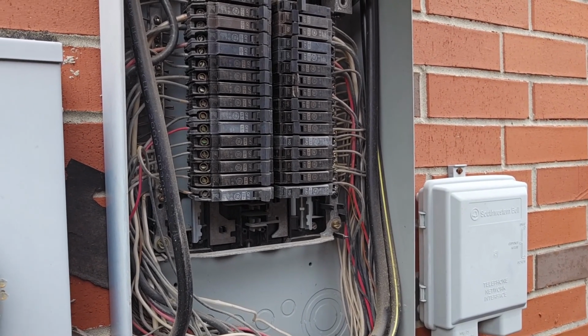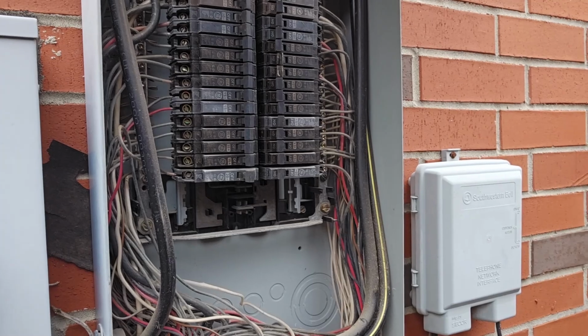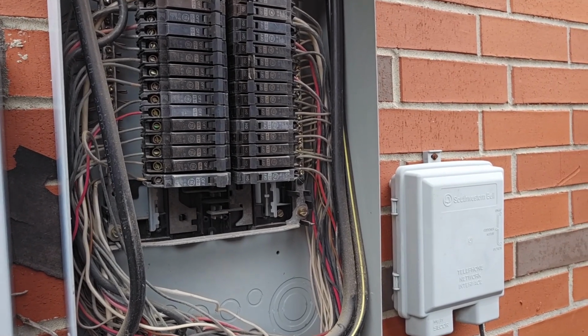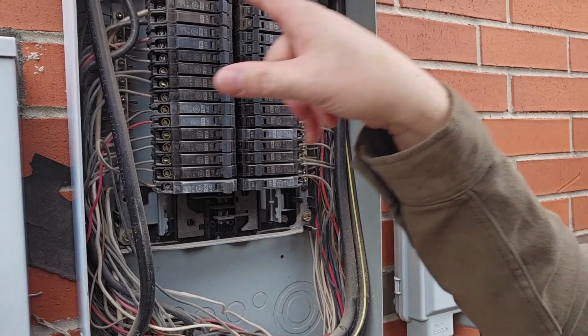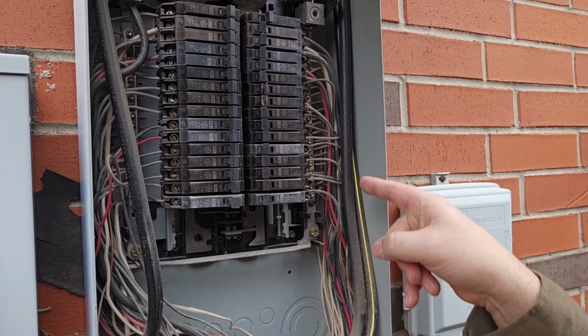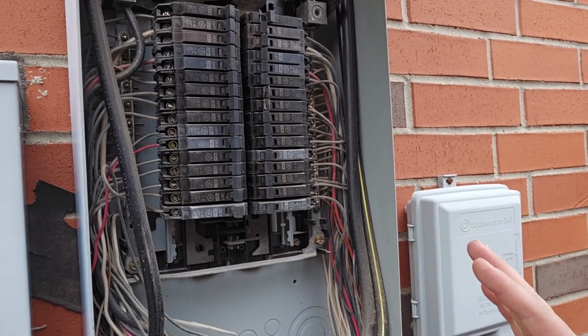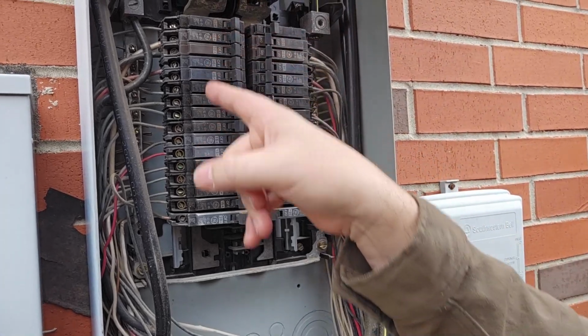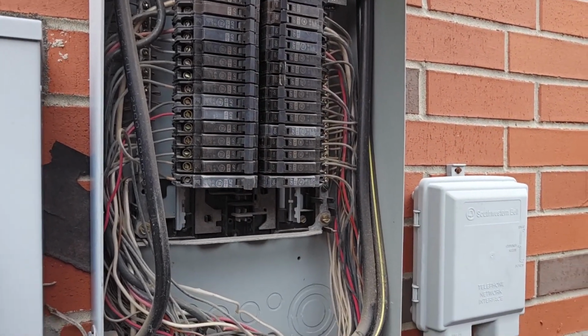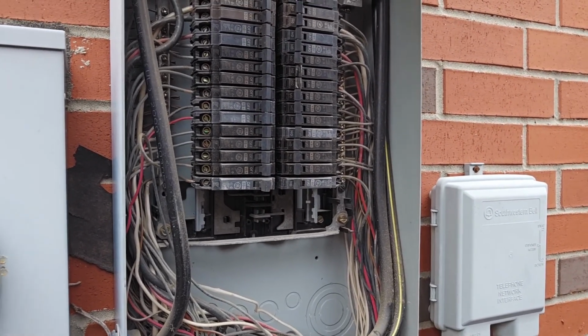All right, well let's put this guy back together, because even though it's not that great of a panel, I did check all my lugs on my ground and neutral bus bars. Everything is tightened down, and I checked all my lugs on every single breaker. They were all torqued down. We were good to go.